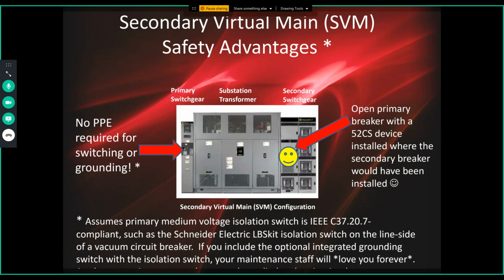And I should add one other thing. In IEC land, in the International Electrotechnical Commission standards land in Europe, integrated grounding switches at medium voltage have been an IEC standard for more than a quarter century. So when Europeans come over to our country and they see us on new equipment, getting out manual grounding cables and hot sticks in PPE, they honestly think we're barbarians. Right? It's a very simple, safe device. Again, if I was in charge of standards, I'd make it a requirement standard in design. I'm not. But in terms of secondary virtual main design, it absolutely makes sense.